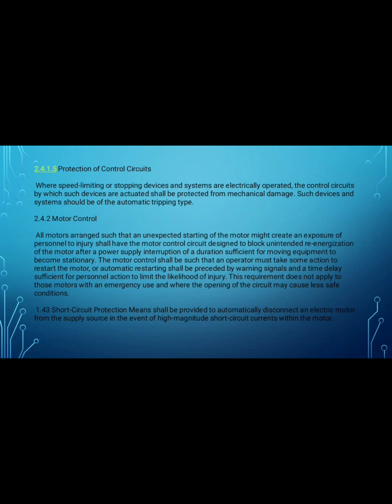2.4.2 Motor control. All motors arranged such that an unexpected starting of the motor might create an exposure of personnel to injury shall have the motor control circuit designed to block unintended re-energization of the motor after a power supply interruption of duration sufficient for moving equipment to become stationary. The motor control shall be such that an operator must take some action to restart the motor, or automatic restarting shall be preceded by a warning signal and time delay sufficient for personnel action to limit the likelihood of injury.